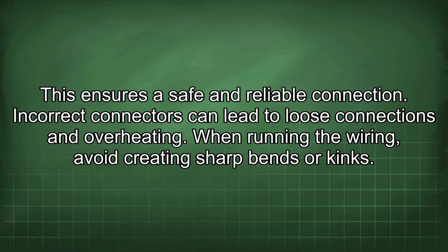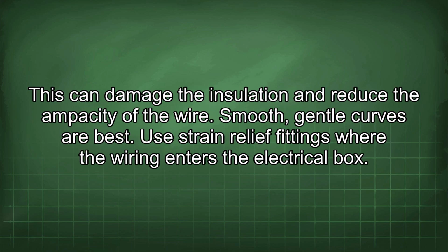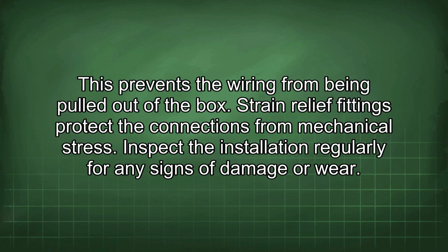When running the wiring, avoid creating sharp bends or kinks. This can damage the insulation and reduce the ampacity of the wire. Smooth, gentle curves are best. Use strain relief fittings where the wiring enters the electrical box. This prevents the wiring from being pulled out of the box. Strain relief fittings protect the connections from mechanical stress.